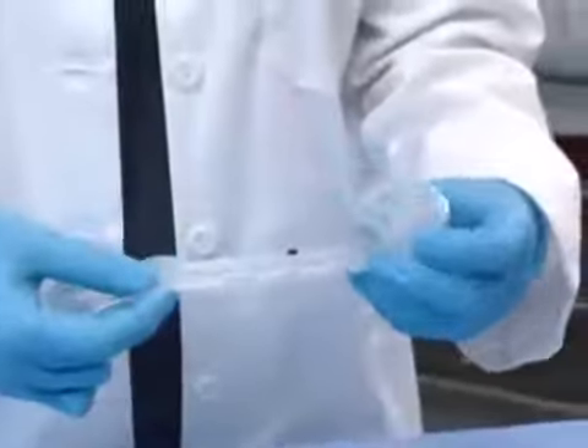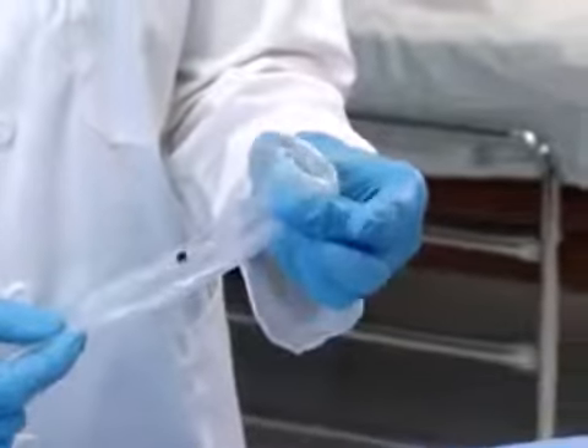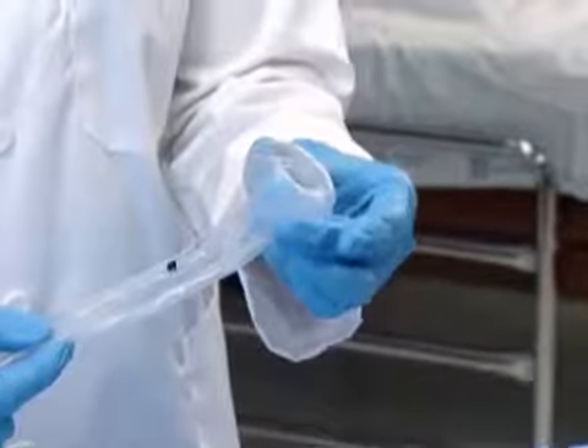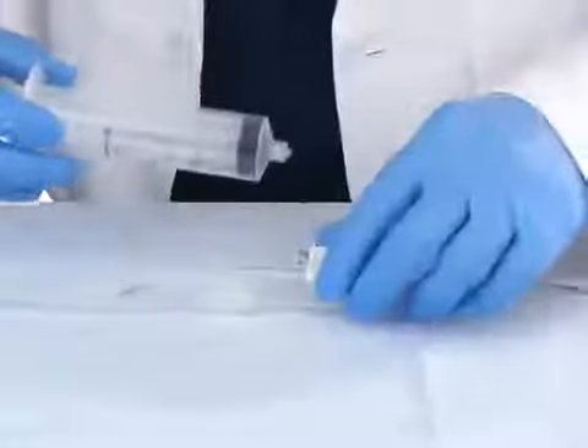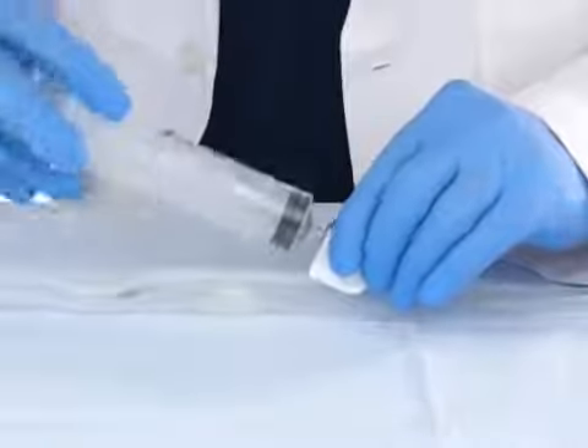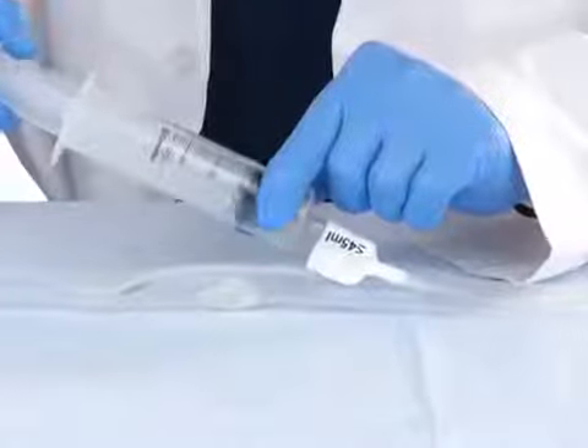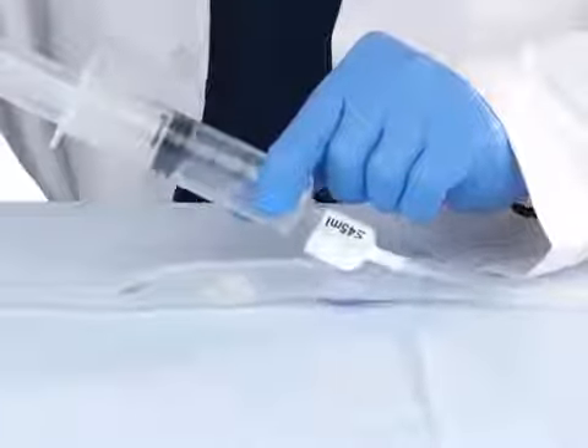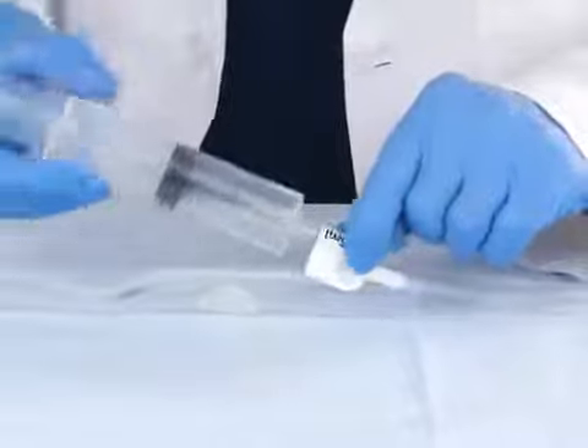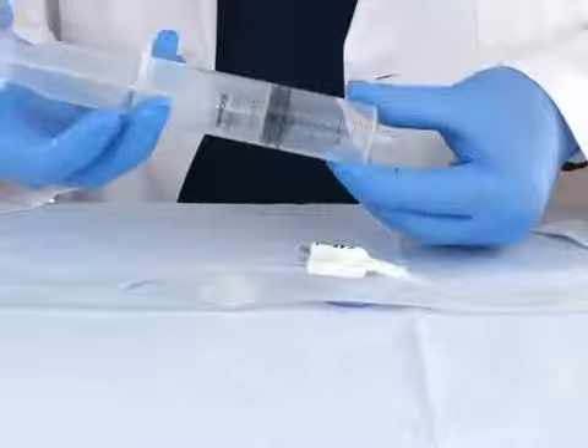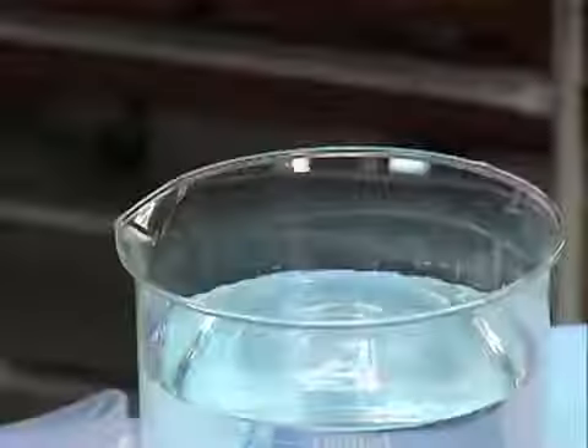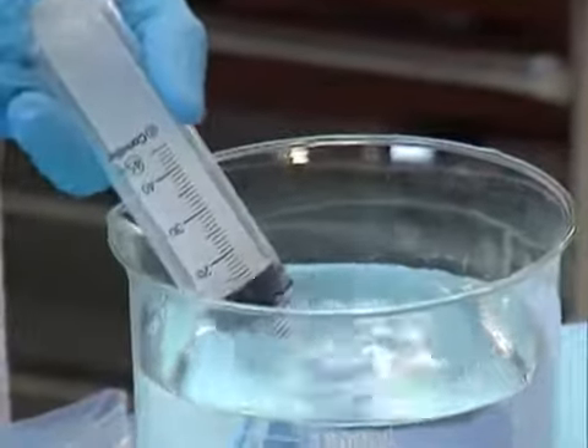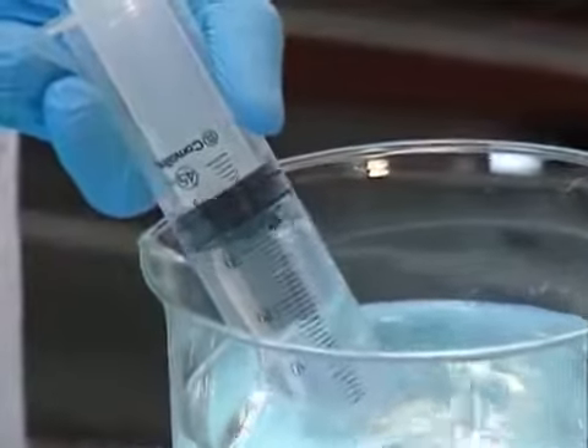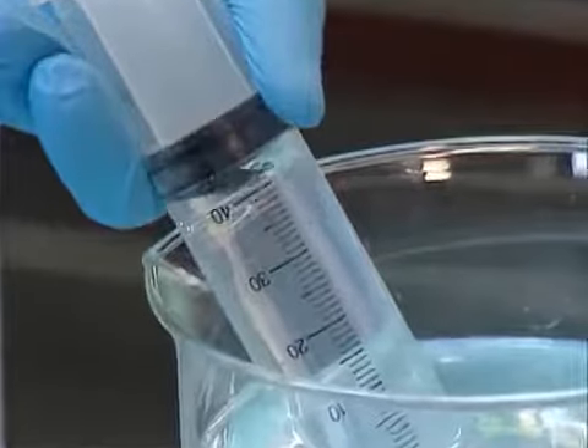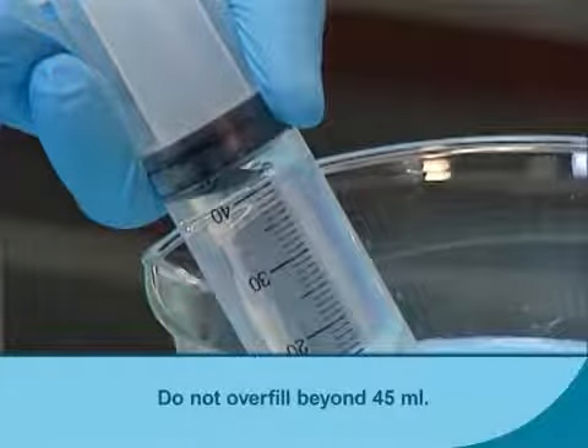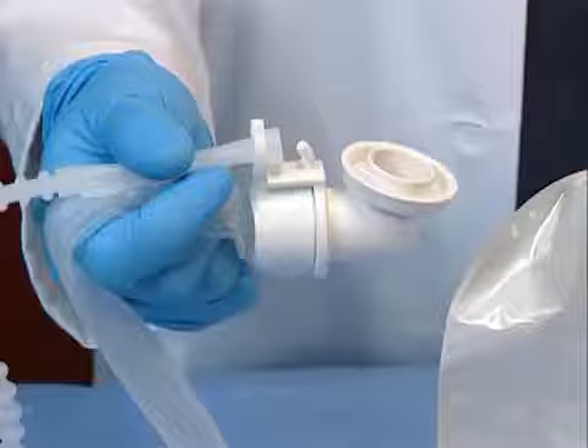When removing the device from its packaging, check to see if there is any residual air in the balloon. If so, remove it by attaching the syringe provided to the inflation port, marked less than or equal to 45 ml, and withdrawing the plunger. Remove the syringe, and prior to filling with water or saline, ensure that the syringe is empty by expelling any air. Next, fill the syringe with only 45 milliliters of water or saline, and connect the syringe to the white inflation port of the catheter. Do not overfill beyond 45 milliliters.